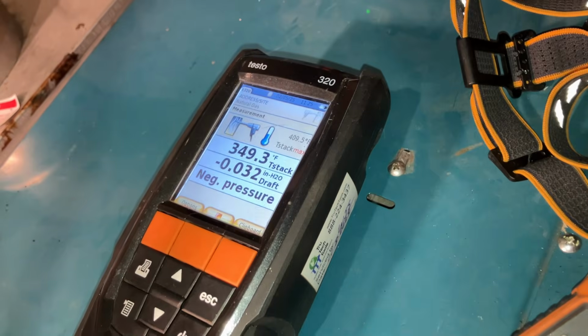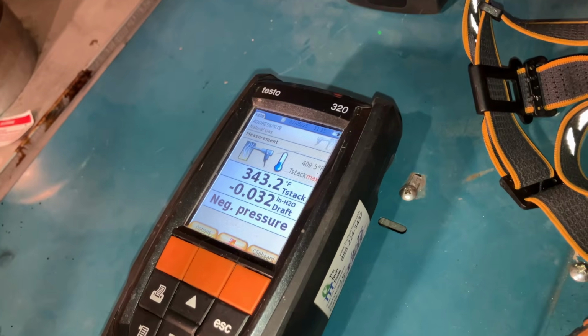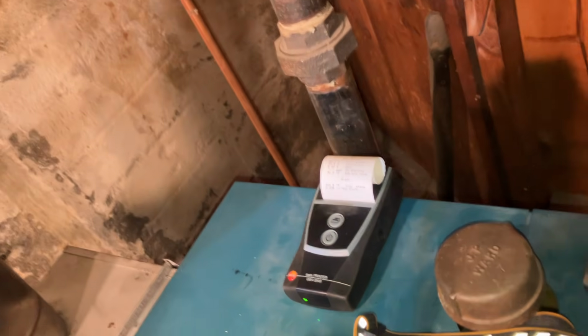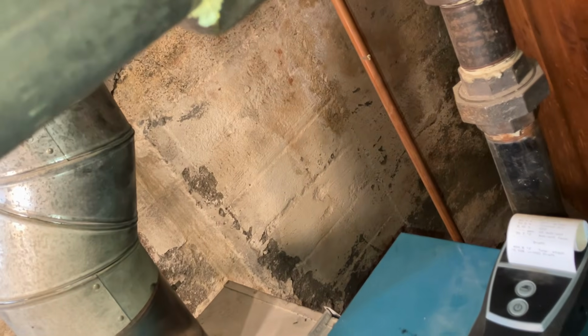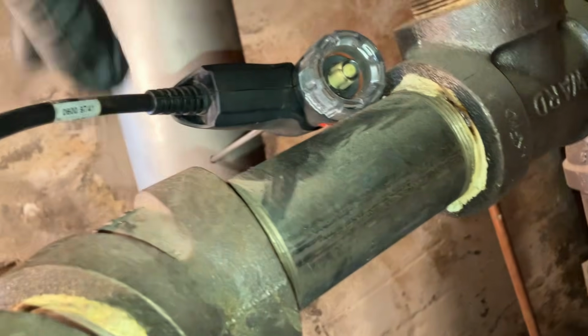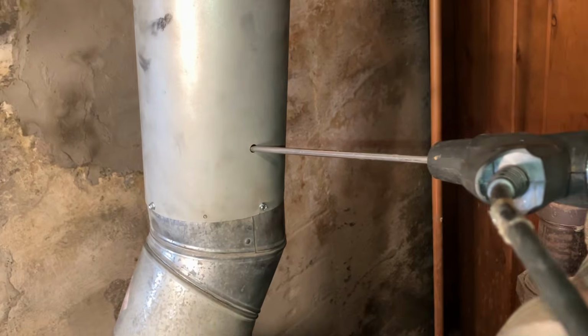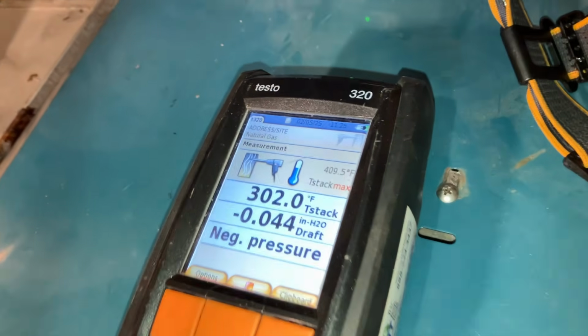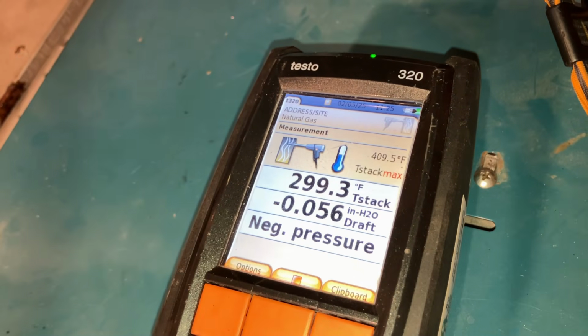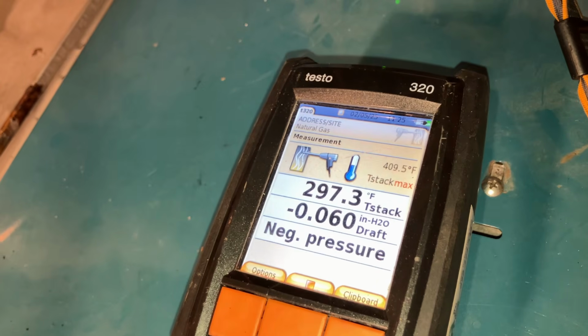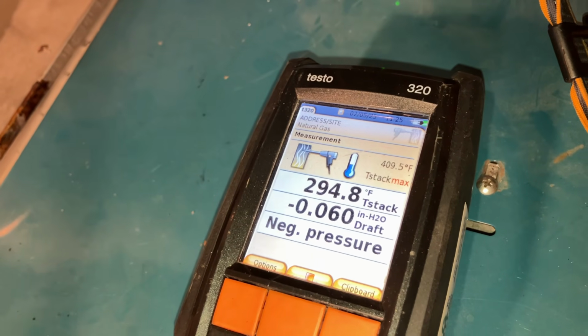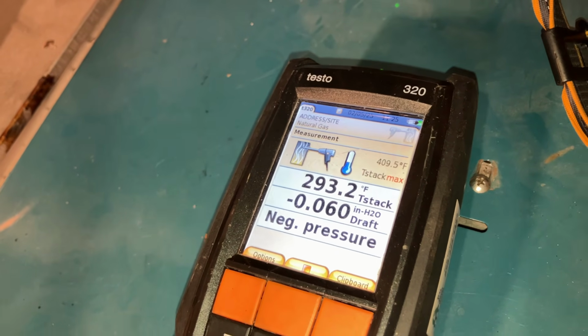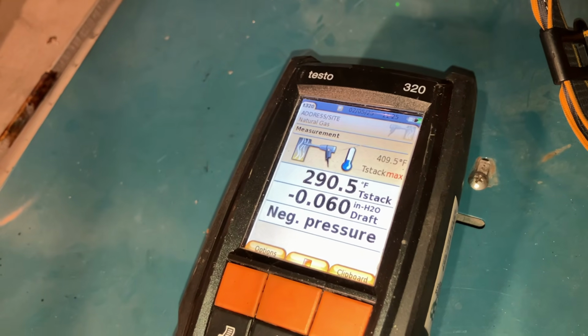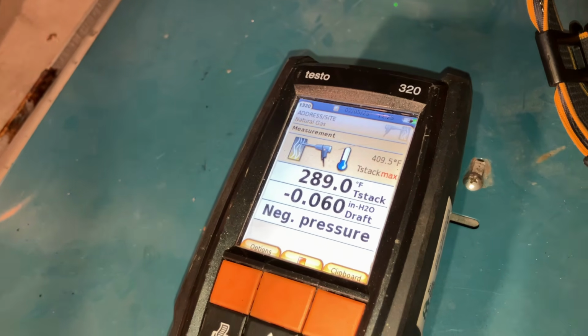Okay. So now we're going to pull that out. We're going to let that go back to something different. And now we're going to take this probe and insert that in the center of that flue. I'm going to let that sit for a minute. And the stack temperature is obviously going to be different. But let's see what the O2 and the negative pressure are in inches of water column.